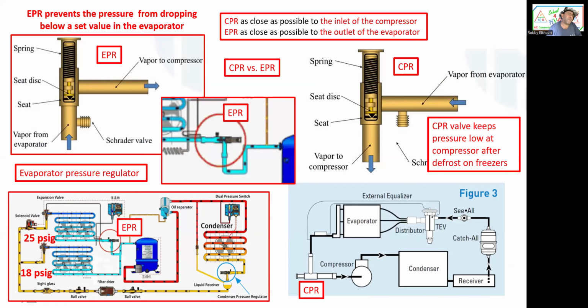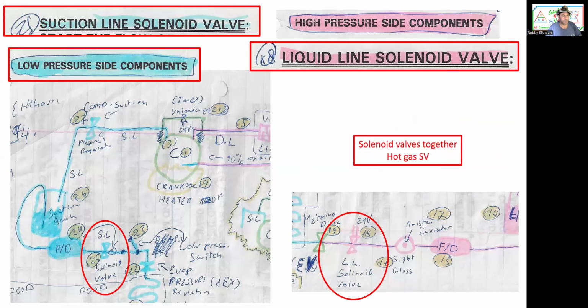So the EPR prevents pressure from dropping below a set value in the evaporator. Another example here: we have an EPR for the 25 psi, and the 18 doesn't need one. So the EPR's job is to keep pressure high. Now the CPR, crankcase pressure regulator, keeps pressure low at the compressor after defrost on a freezer. And there's the location of it: one is before the compressor and one is after the evaporator. All right, let's move on.